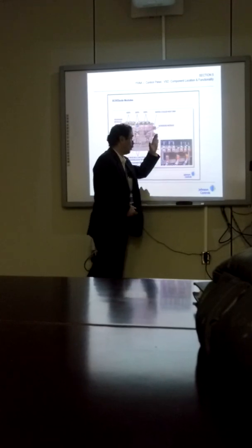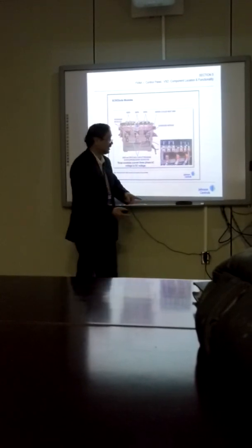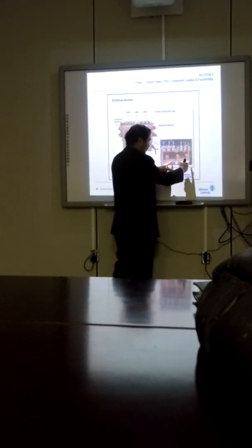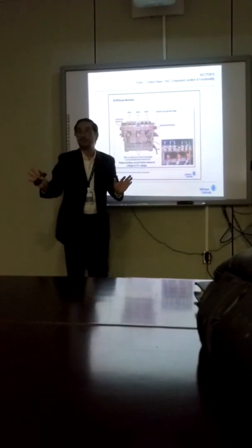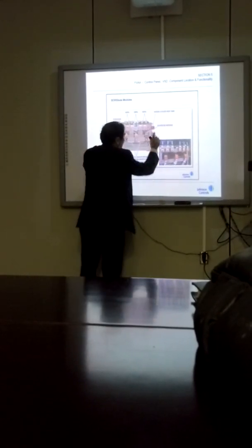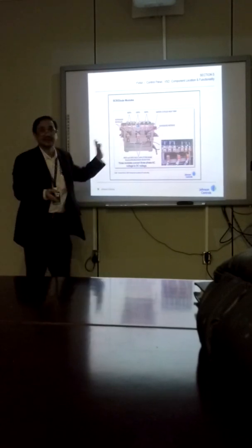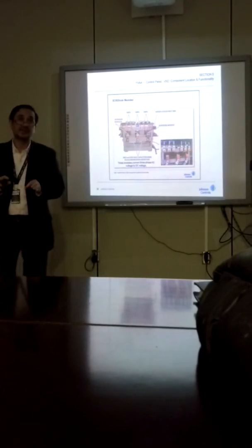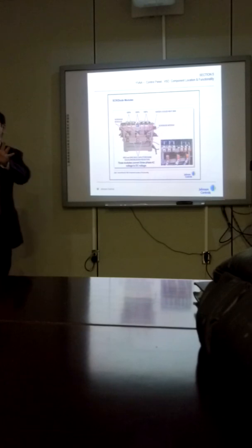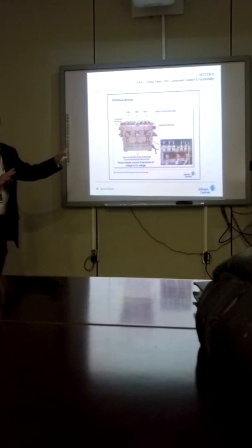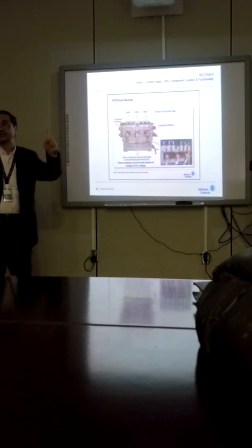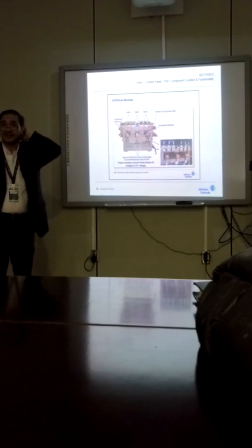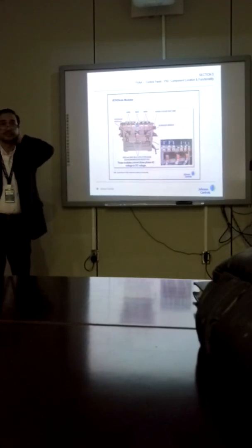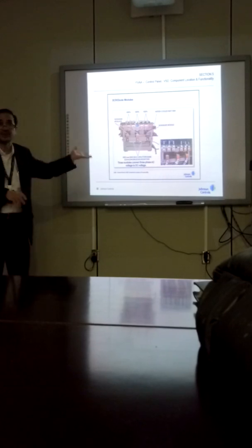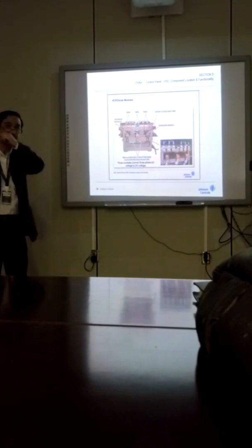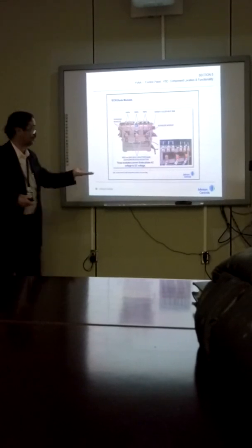You have to wait 15 minutes, then put your meter on AC here. Check, no power at all, and then DC, no power at all. Then that's the time you can handle it. But with care, okay? Make sure that everything will be safe. Look, the first priority here is safety. The second is your other team. Third is the machine. Machine we can replace, but not humans. Okay? That's the main point here.